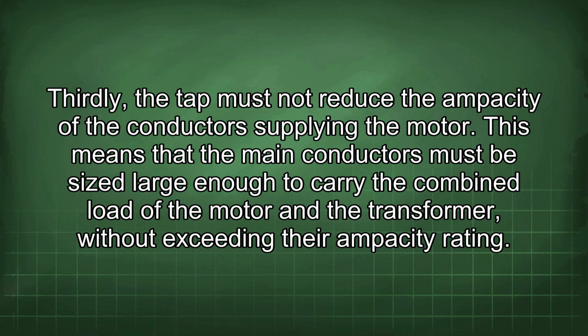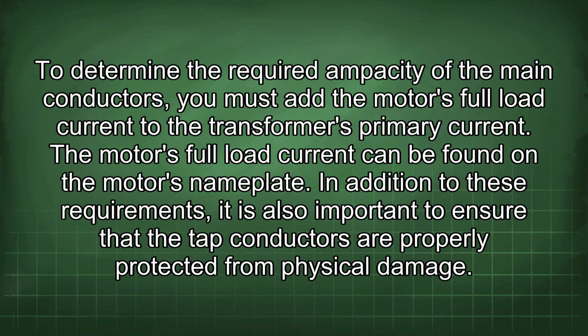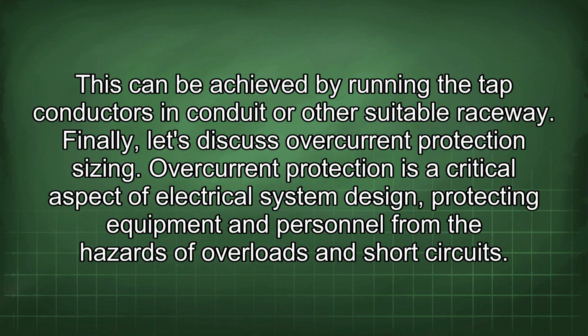This means that the main conductors must be sized large enough to carry the combined load of the motor and the transformer without exceeding their ampacity rating. To determine the required ampacity of the main conductors, you must add the motor's full load current to the transformer's primary current. The motor's full load current can be found on the motor's nameplate. In addition to these requirements, it is also important to ensure that the tap conductors are properly protected from physical damage. This can be achieved by running the tap conductors in conduit or other suitable raceway.